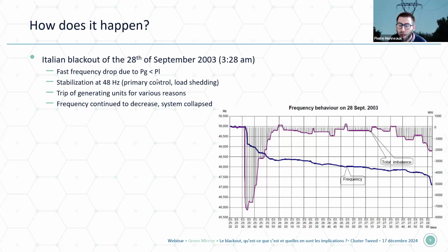But then primary control acted and load shedding helped to stabilize the frequency. So you see that quite quickly, after a few tenths of seconds, the power imbalance was brought back to 0. But nevertheless, the frequency continued to decrease. Even if it was brought back at some point to 0, it became negative again afterwards because some generating units tripped for various reasons. They were exposed to a fast, unexpected frequency transient, and so they had internal problems. They had some difficulties to face that fast frequency transient, and they were disconnected from the grid by some protection system. That led to a continued power imbalance. And so the frequency continued to decrease until it reached 47.5 Hertz.